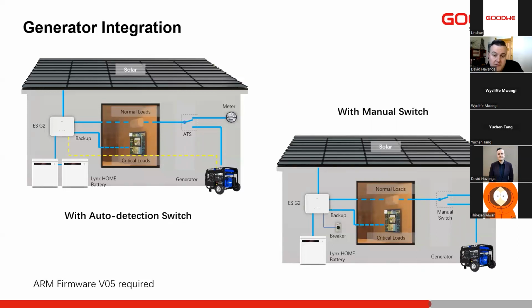Then the ES Generation 2 is our only device with this function, which is generator integration. We also have a separate dry contact to switch on automatic start generators. With this, we can configure different battery percentages, or we can just manually switch it on as well. If you have an ATS site with an auto start generator, we can program that to say once the batteries reach a certain percentage, they should start the generator, charge the batteries up until they are full or until the percentage you like, and then we switch the generator off again.